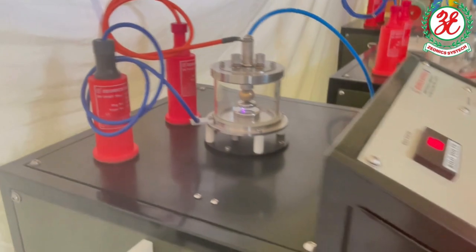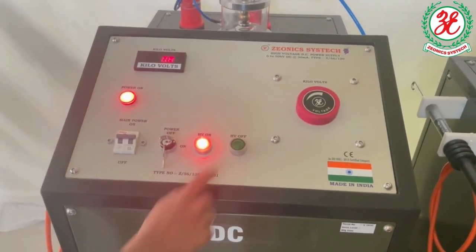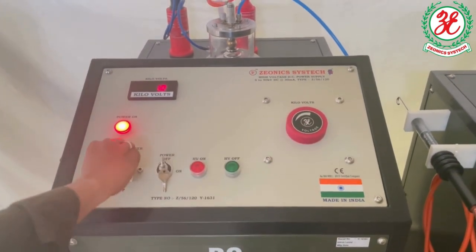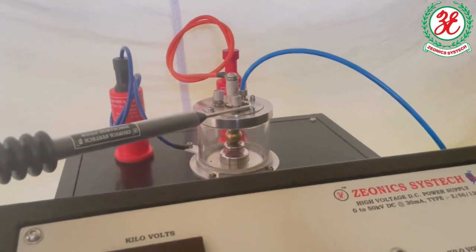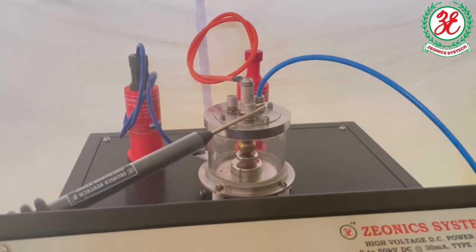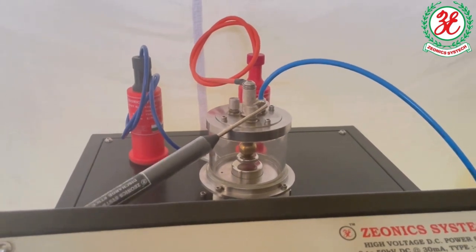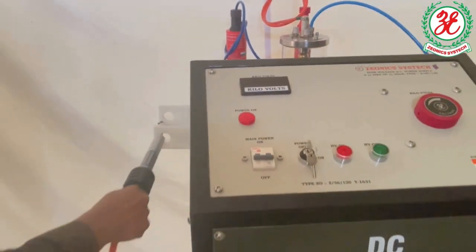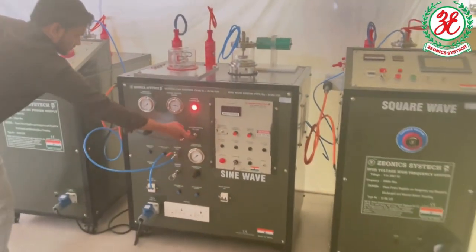Once your experiment is complete, to turn off the system, reduce the voltage, switch off the high voltage, turn off the key switch, switch off the MCB, discharge the plasma chamber before touching. This is especially important for the DC system as there is an internal capacitor which will remain charged if not completely discharged. You can hook it here for a minute or two if you like. Once it's complete, replace the system, and this completes the operation of the entire set of 3 systems.